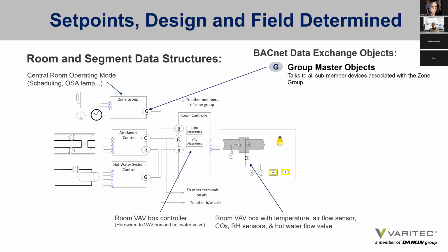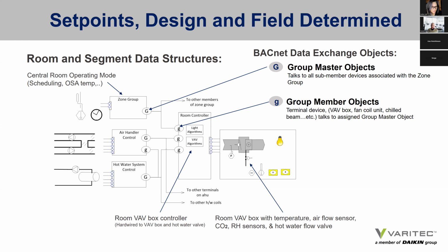The larger master group objects actually distribute and communicate the overall design parameters that each individual zone will take into account while maintaining its local discrete conditions. And then you have group member objects, such as terminal devices, VAV boxes, fan coil units, chilled beams, that talk to individual group master objects or a zone group, which can be looked at in a VAV system as being an air handler. So these are all interconnected, exchanging information from the zone to the zone group and from the zone group to the zone, so that there's constant dialogue going on between these master and member objects.